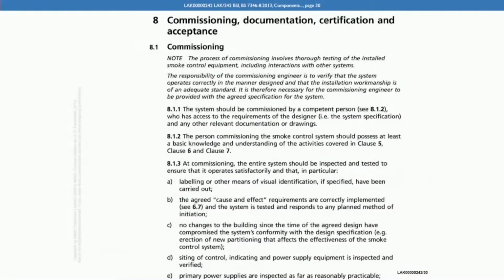And if we go to look at clause 8.1 on page 30 of it, under commissioning, we can see in the notes at the top, it says the process of commissioning involves thorough testing of the installed smoke control equipment, including interactions with other systems. And then under that, the responsibility of the commissioning engineer is to verify that the system operates correctly in the manner designed and that the installation workmanship is of an adequate standard. It is therefore necessary for the commissioning engineer to be provided with the agreed specification for the system.